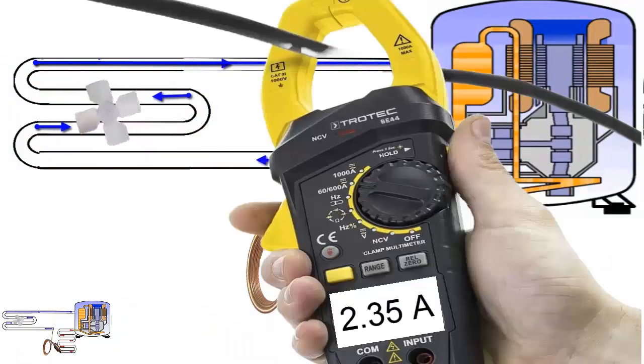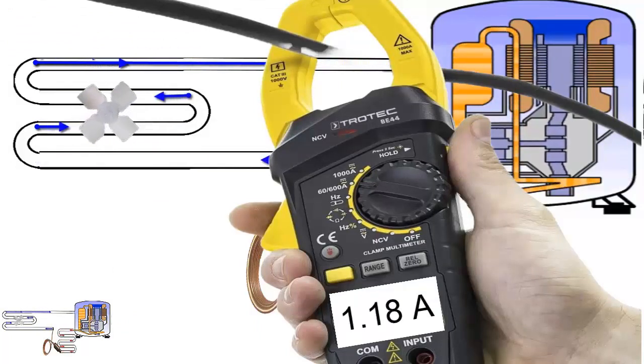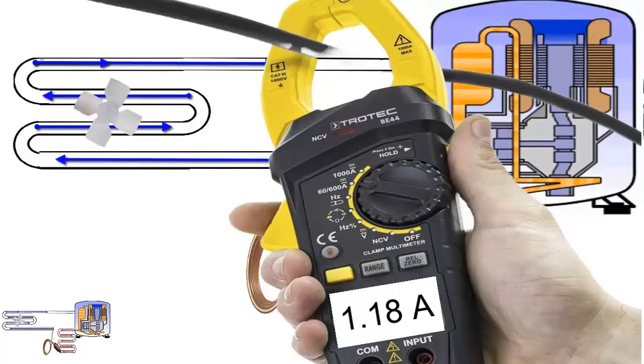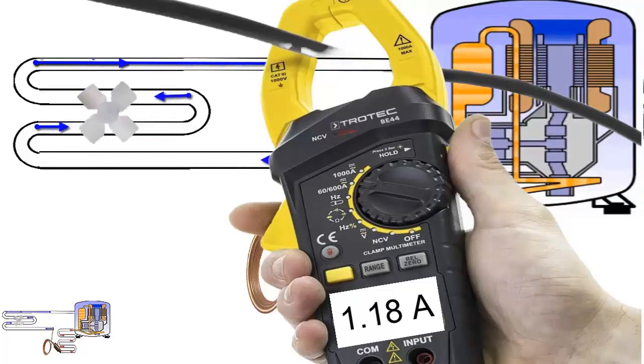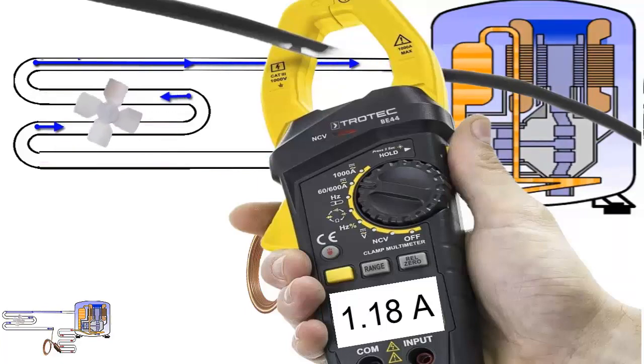The nominal electrical consumption of the 1/4 HP compressor, known as RLA, is 2.35 amperes at 110 volts and 1.18 amperes at 220 volts. You can verify this value using the amperometric clamp.